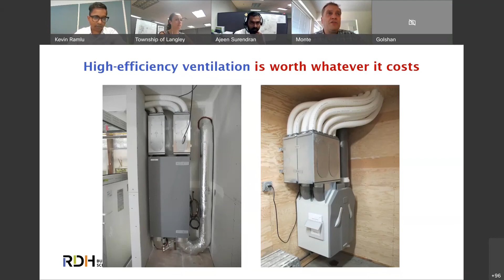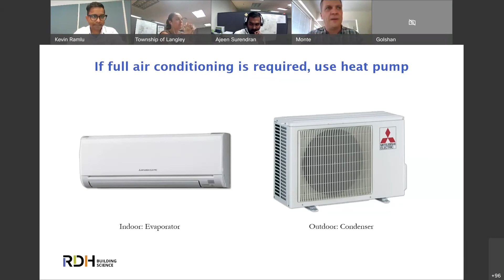And then finally, if you do have to go to cooling, if you need full air conditioning, realize that if you set up a heat pump system for the whole place, you get heating and air conditioning at high efficiency in one. If you get pushed to air conditioning, the first thing you do is yank out the gas line, because you don't need a boiler or furnace anymore at that point. You're going to put in the heat pump for air conditioning, and therefore you have it for heating as well. You don't want to pay for two systems, having a gas system do the heating and a heat pump system do the cooling. Do it once with a great multi-split heat pump, and you're done.